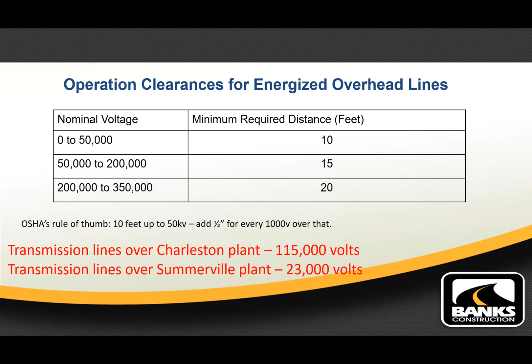Here's a chart for operation clearances for energized overhead power lines. OSHA's got a 10-foot rule, but depending on the voltage, you could need a little bit farther clearance distance. For example, the transmission lines over the Charleston plant are 115,000 volts, so we'd want a 15-foot clearance. The transmission lines over the Summerville plant are 23,000 volts, so we should be good with that 10-foot clearance rule.